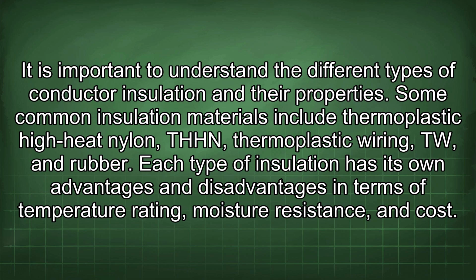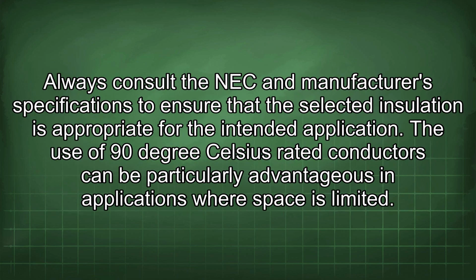It is important to understand the different types of conductor insulation and their properties. Some common insulation materials include thermoplastic high-heat nylon, THHN, thermoplastic wiring, TW, and rubber. Each type of insulation has its own advantages and disadvantages in terms of temperature rating, moisture resistance, and cost. Always consult the NEC and manufacturer's specifications to ensure that the selected insulation is appropriate for the intended application.